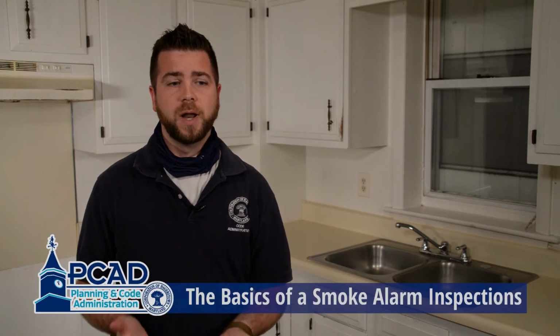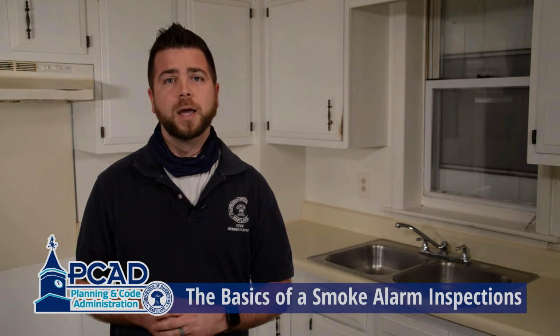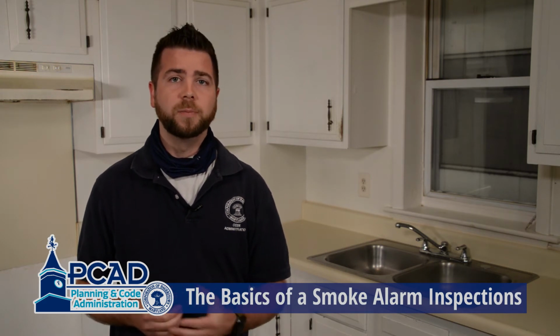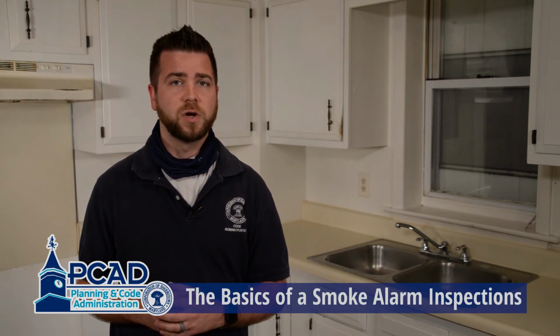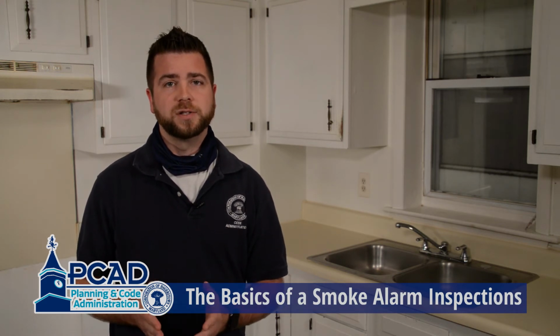kitchen. When discussing smoke alarms in a kitchen, we want to make sure that they are replaced every 10 years per Maryland law. And all battery-powered smoke alarms should have a non-replaceable 10-year battery installed in them. And be sure to follow manufacturer instructions when installing and caring for your smoke alarms. And also make sure they are not installed within 10 feet of a cooking appliance.